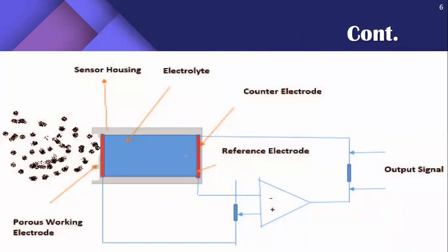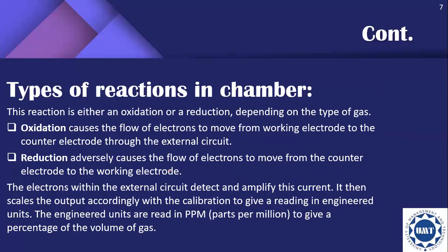When a gas enters the chamber, this reaction is either an oxidation or a reduction depending on the type of gas. In oxidation, there is a flow of electrons from the working electrode to the counter electrode through the external circuit. The external circuit detects and amplifies this current, then scales the output with a calibration to give a reading in parts per million, which is used to give a percentage of the volume of the gas.